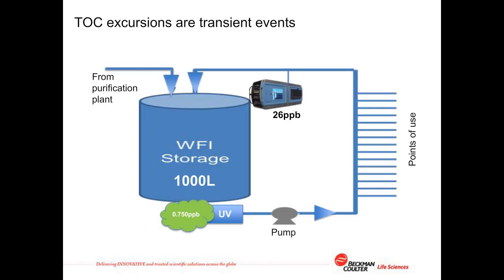Now TOC levels in the loop return to their safe low TOC value, but it's too late, because during the excursion the levels of TOC at the points of use were outside the pharmacopoeial limits, and any batches being manufactured at that time cannot be released into the market. What makes the situation worse is there's no way to carry out root cause investigation analysis to find the likely sources of the TOC excursion, as all the evidence has been effectively destroyed and diluted in the water storage tank and using the UV lamp. So there's no way to put preventative action in place to stop the recurrence of the excursion again at a later date, thus compromising future batches of product as well.